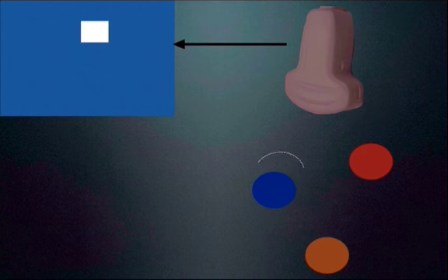We can see our ultrasound machine generating the pulse. It goes out and hits multiple targets, and then you get return of signals. Those signals return at different times. And because, again, we know the speed of sound in soft tissue, and we know the time that it took for the sound to return, we can then apply our appropriate pixel to the appropriate location on the screen.